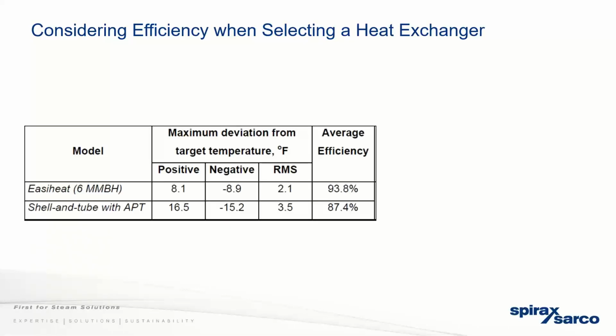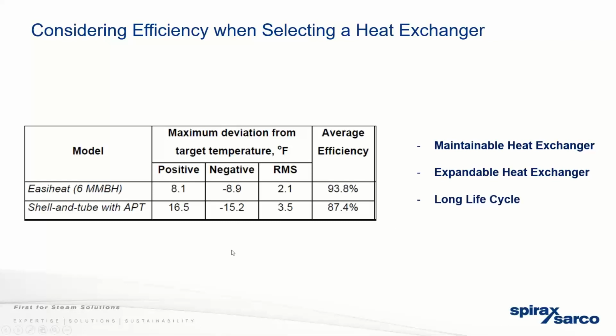Considering efficiency in selecting the heat exchanger, we had a Natural Gas Technology Center, an independent group that all the natural gas providers across the country work with, do a study of a system operating under vacuum, plate and frame versus shell and tube. And we saw about a 7% efficiency gain. Other benefits of plate and frame: they are maintainable. You can pull apart those plate packs and clean them, and you can expand them. You can add plates if you want to change a process and you're adding more hose stations or increasing the processing side. And there's a long life cycle by operating under vacuum where the temperatures are quite cold.